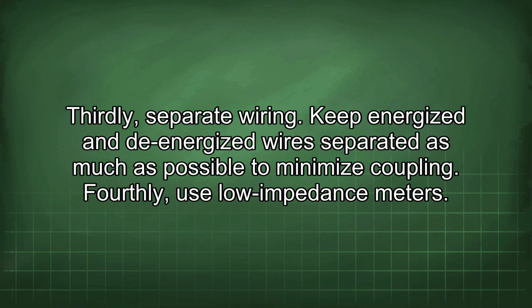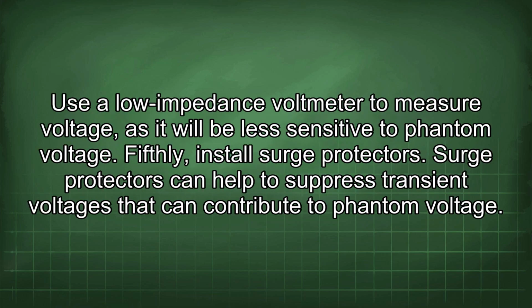Fourthly, use low impedance meters. Use a low impedance voltmeter to measure voltage, as it will be less sensitive to phantom voltage. Fifthly, install surge protectors. Surge protectors can help to suppress transient voltages that can contribute to phantom voltage.